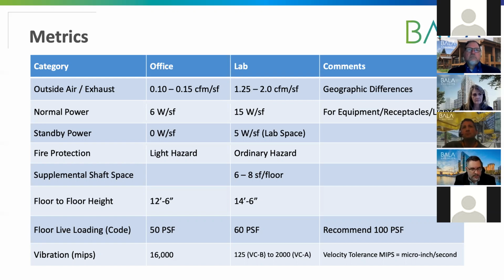Next, we look at supplemental shaft space. For a typical conversion with 1 to 2 CFM per square foot, we're seeing roughly 6 to 8 square feet of extra area required on a floor to accommodate the new outside air and exhaust. To put that in perspective, this is for a building footprint of about 20,000 square feet. If you have a larger footprint, up to 40,000, you'd need basically twice this amount - 12 to 16 square feet of shaft space. But again, this just gives you a rough idea of the area to allocate when considering conversion.